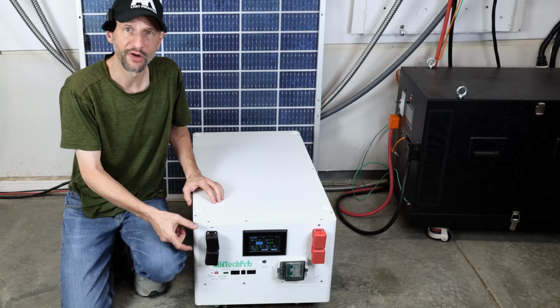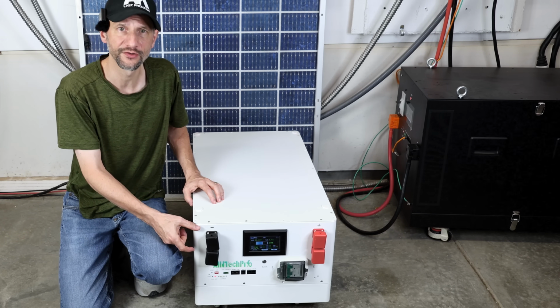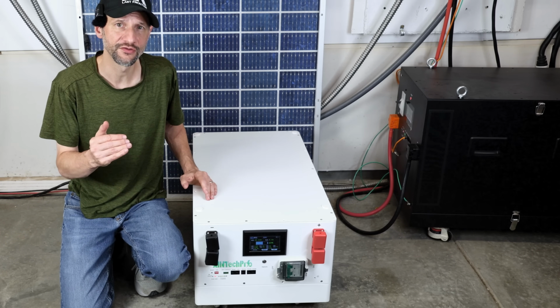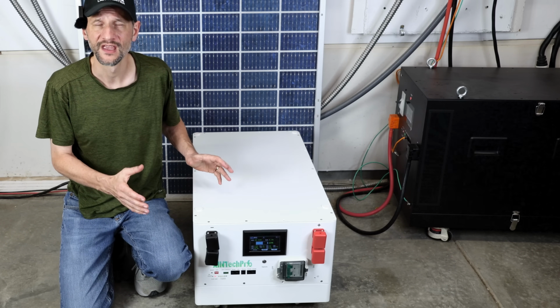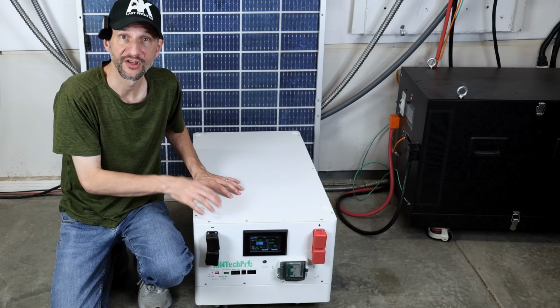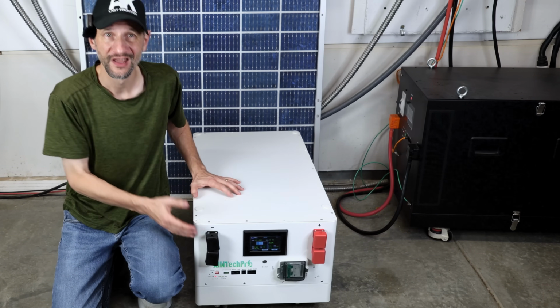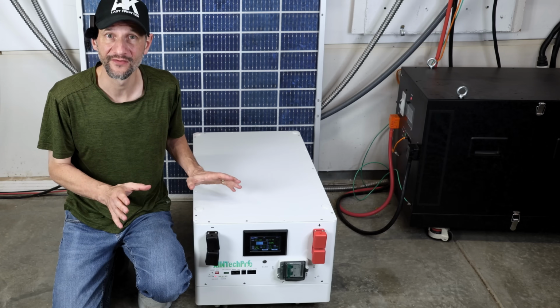With the addition of the bus bar and 4-gauge wire conductors, I could make it as much as 140 and still have good margin. If you keep the 6-gauge conductors that come with the unit and no bus bar, I would set it to a max of 65 amps.